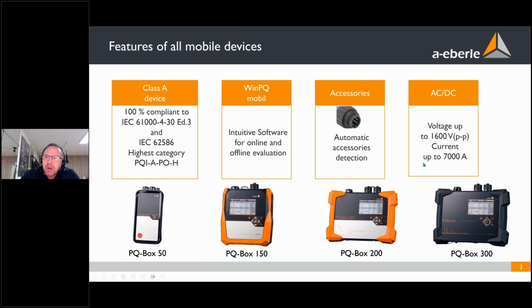We're getting more and more DC applications in our network, to measure in solar plants and to measure in industrial environments. Therefore, all of our analyzers can measure AC and DC, voltage, current, DC power. DC, we can measure up to 1600 volt if you use phase-to-phase measurement. The current is only limited by the Rogowski coils or current clamp, so even 7000 amps will not be the limit. It depends on the clamps.